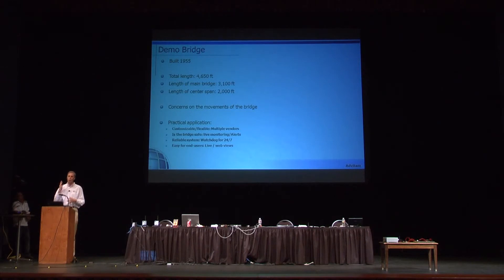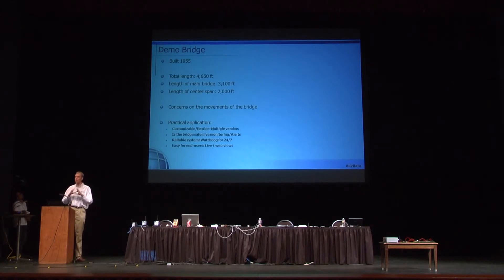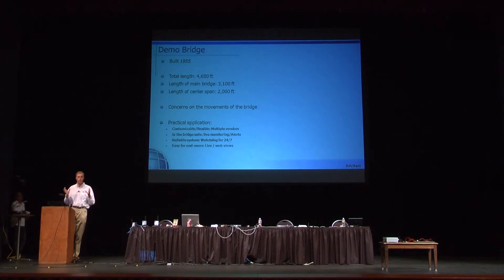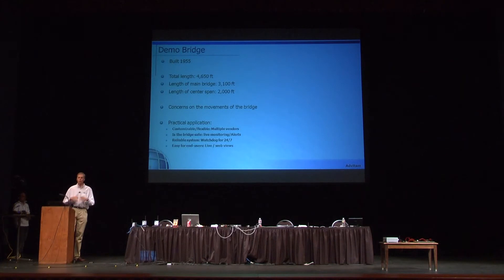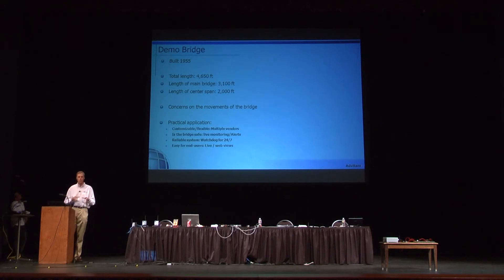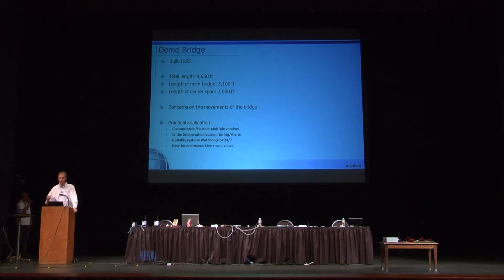When we designed the system, we had four practical items in mind. First, we did something customizable because we used sensors from different vendors, so we needed a system that was flexible. Second, for the client, the main question is: is the system safe? For that, we have live monitoring and the ability to set thresholds and alerts directly on site, and to receive those alerts via cell phone or email. Third, we need something reliable — a system that works 24/7 and warns us if something goes down, like power or communication. Finally, something very user-friendly for the client.